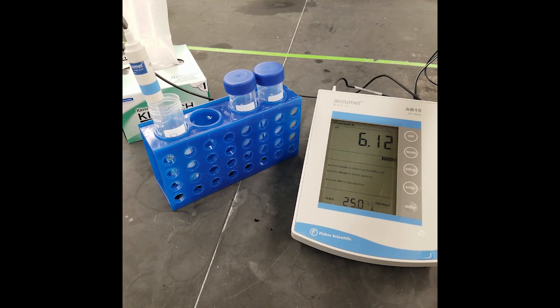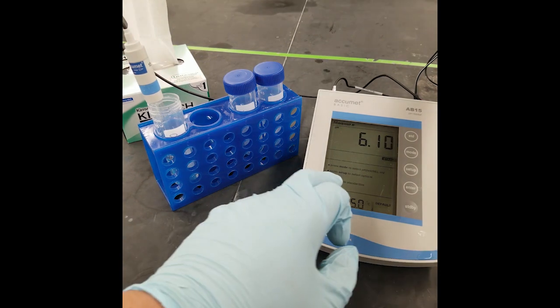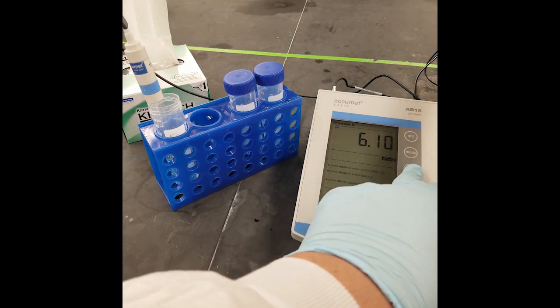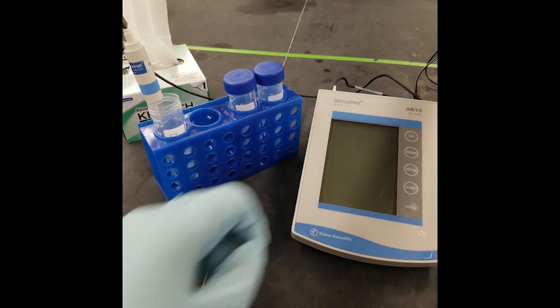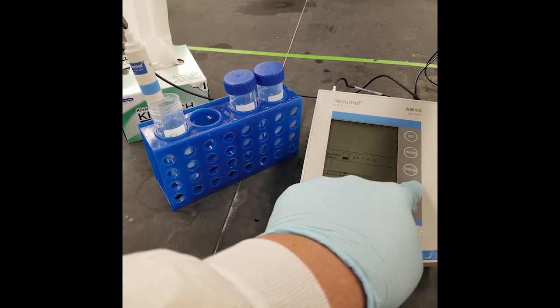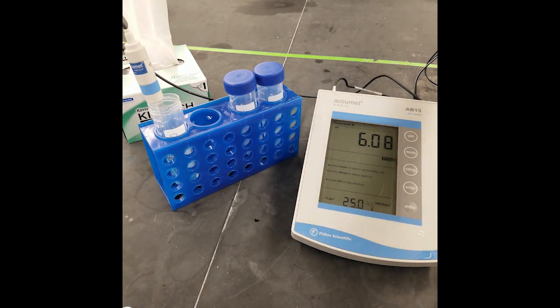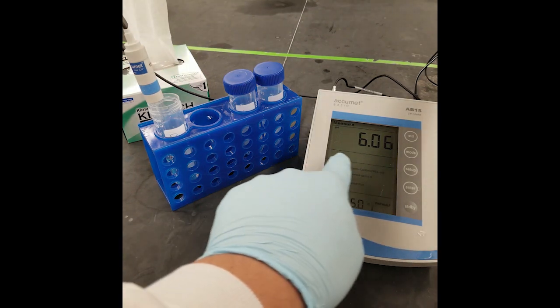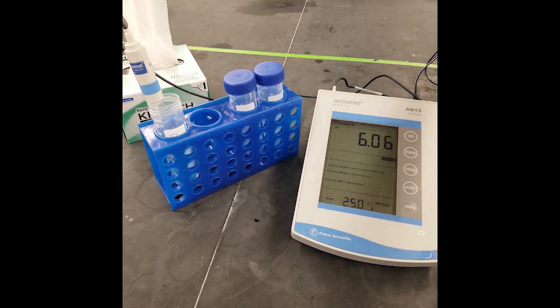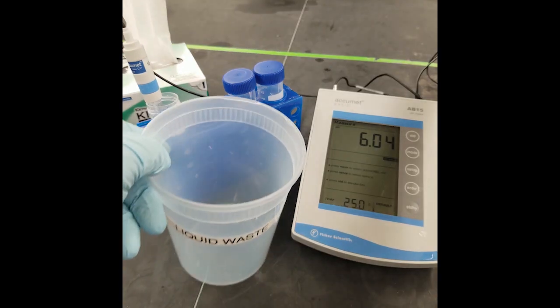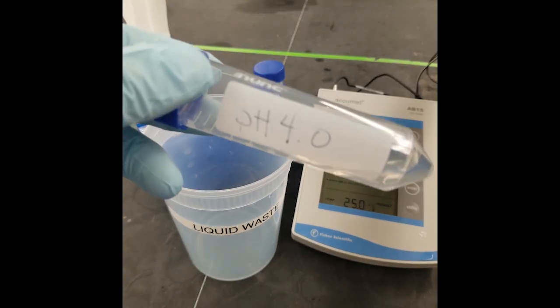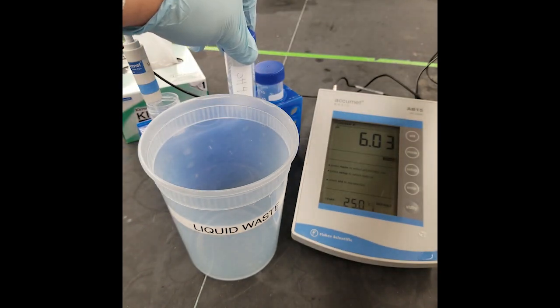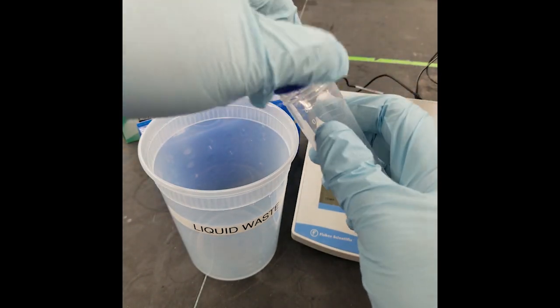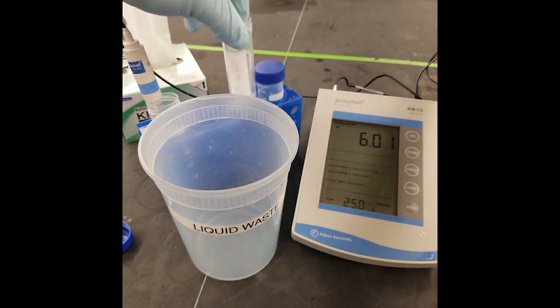So when you're ready to calibrate your pH meter, you want to make sure that whatever previous calibrations were on there get erased, and so you're going to hit the setup button twice and hit enter. Notice that there I didn't have any previous calibrations, so all I did was go back to the same screen that I had before. So now what I want to do is standardize my pH meter against the pH 4 solution. So I'll go ahead and uncover that 50 mL conical tube and just place it in my tube rack.